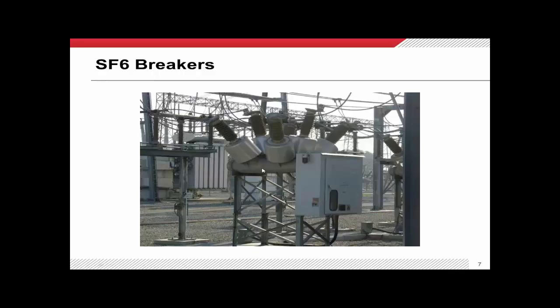Here's another circuit breaker at a completely different voltage — a 72 kV class circuit breaker — but all the same features are present. We have a control cabinet in the front, three poles, and again the interrupter is inside the cylinder, which is full of SF6 gas as the insulating medium. The CTs are located underneath the aluminum cowlings. On top of the bushings are pads to connect conductors, leading off to disconnect switches on either side of the breaker.